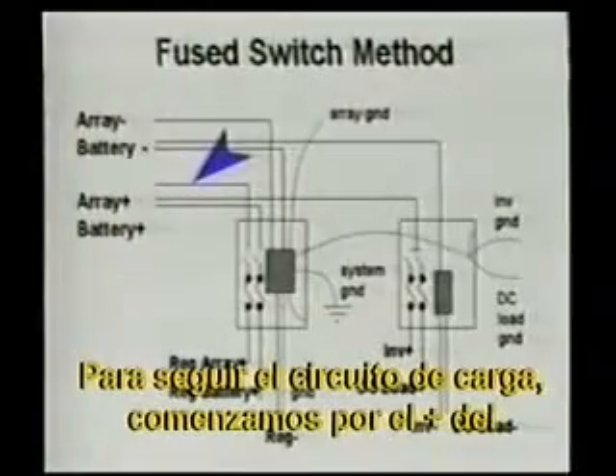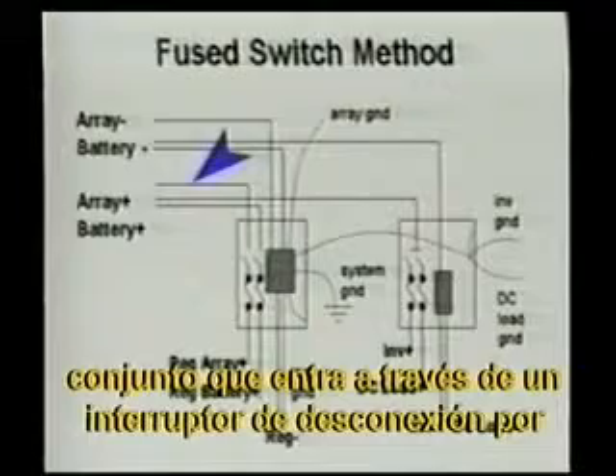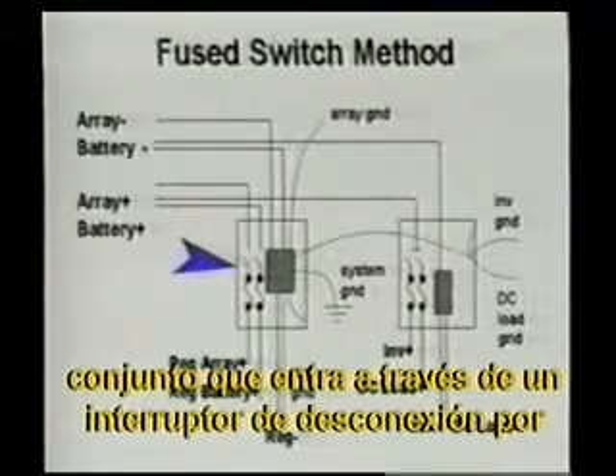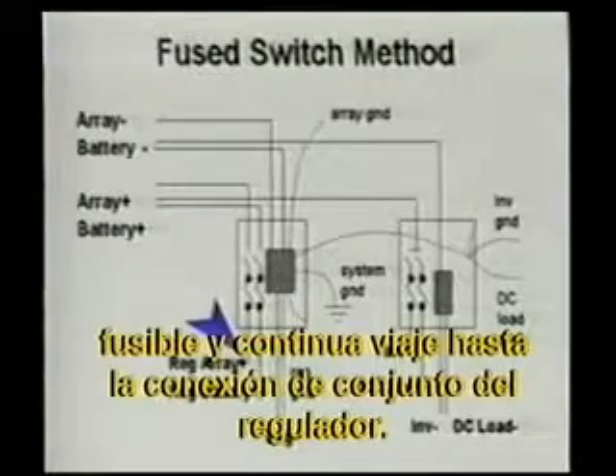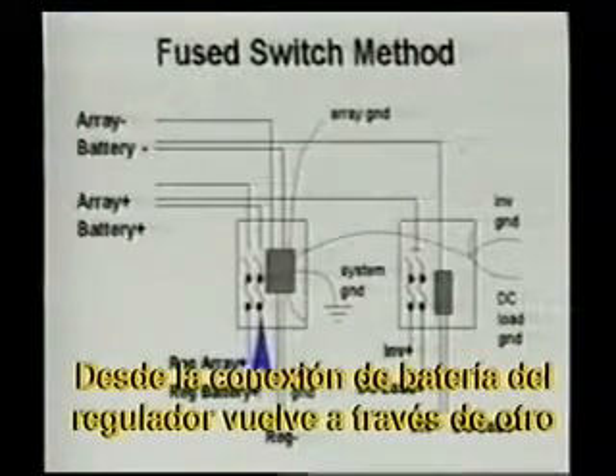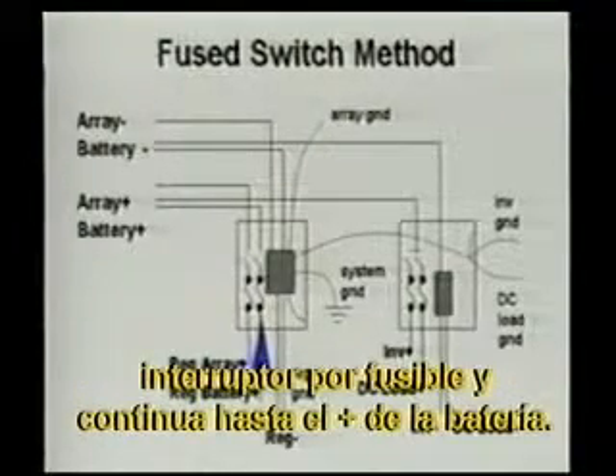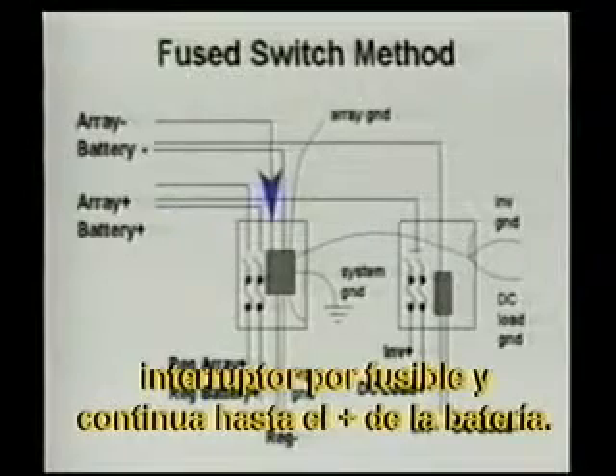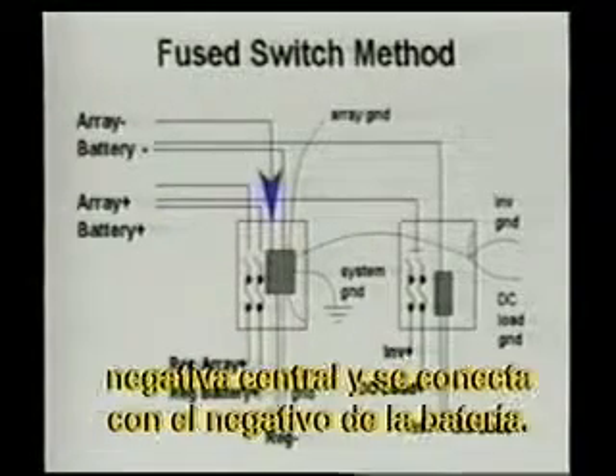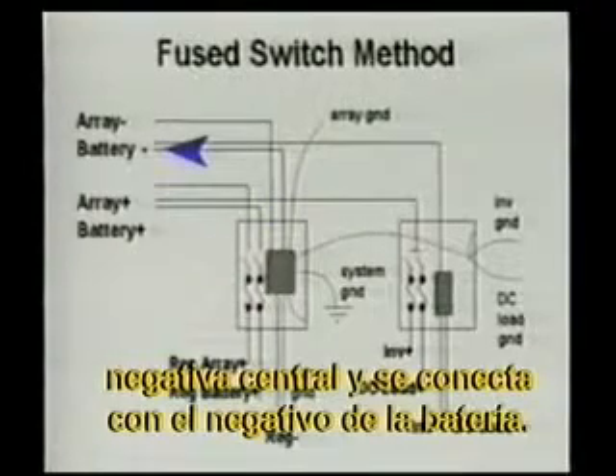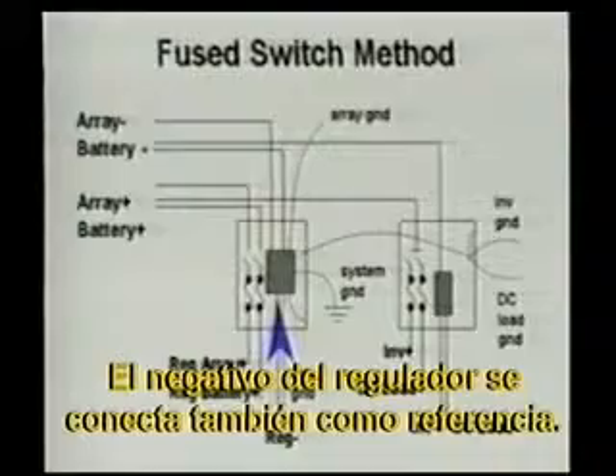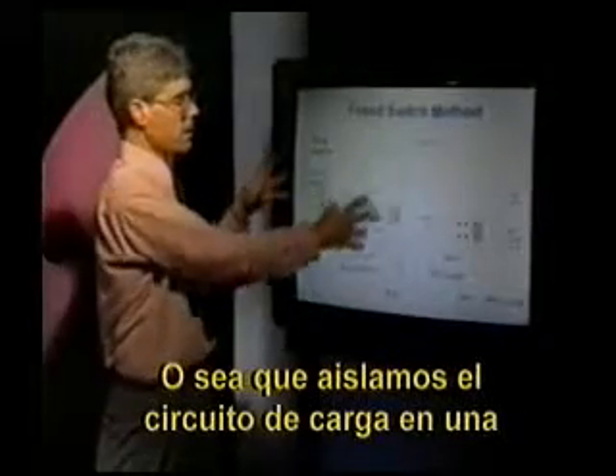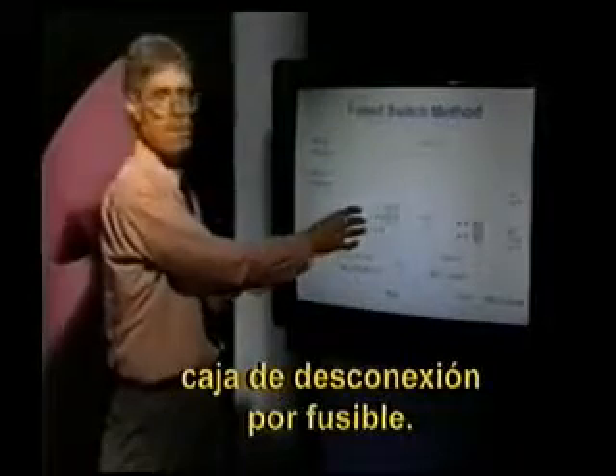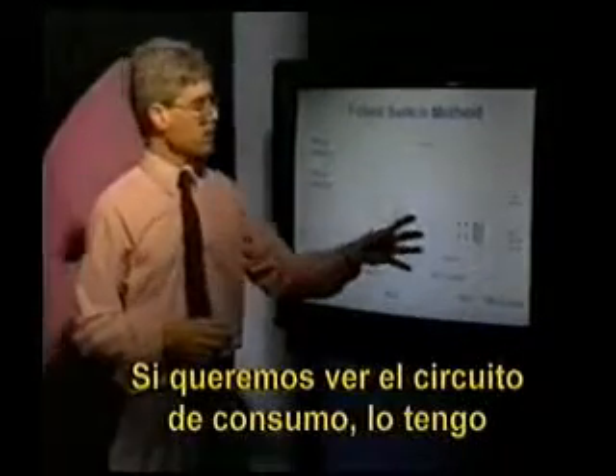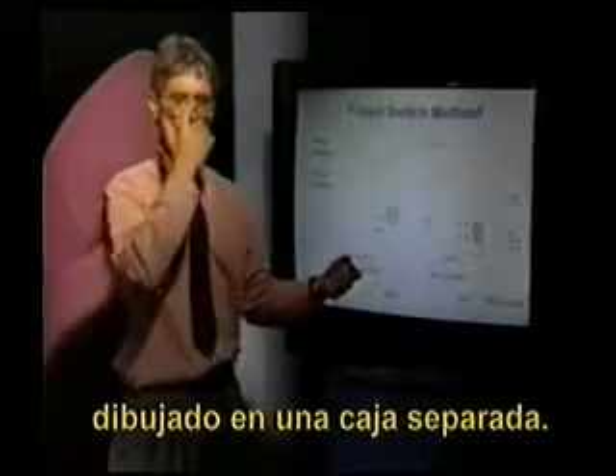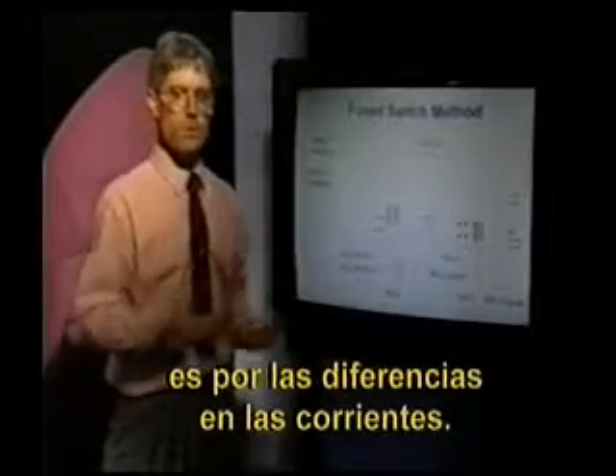To follow the charging circuit, we begin with the array plus, which comes in through a fused disconnect switch and travels on to the regulator array connection. From the regulator battery connection, it goes back through another fused switch onto our battery plus. The negative connection from the array comes into a central negative wiring, connects to the battery minus. The regulator negative is connected as well as reference. So we've isolated our charging circuit in one fused disconnect box. If we want to look at our load circuitry, I have it drawn in a separate box. I think that would be typically the case, and the reason is because of the differences in current.